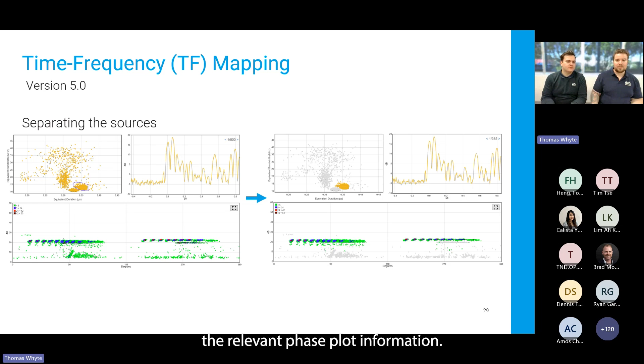So in the second source selected, we can see that the phase plot has changed, the graph has changed, and we're highlighting this cluster here, which looks like a bit of floating metal. Now here's the third and final PD source in this example, a vertical cluster of activity highlighted in the TF map. This pattern is typical for an internal void, and if it had been more active on both sides, you'd see 2 vertical patterns here, slightly varied in time.